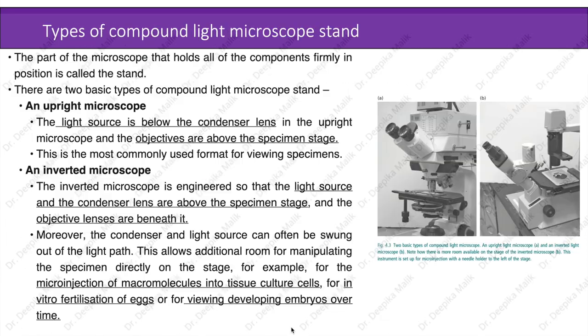There are two basic types of compound light microscope stands. In an upright microscope, the light source and condenser lens are below the stage and the objective lenses are above the specimen stage — the most commonly used format. In an inverted microscope, the light source and condenser lens are above the specimen stage and the objective lenses are beneath it. The condenser and light source can often be swung out of the light path, allowing room for manipulating the specimen directly on the stage — for example, for micro-injection of macromolecules into tissue culture cells, in vitro fertilization of eggs, or viewing developing embryos over time.